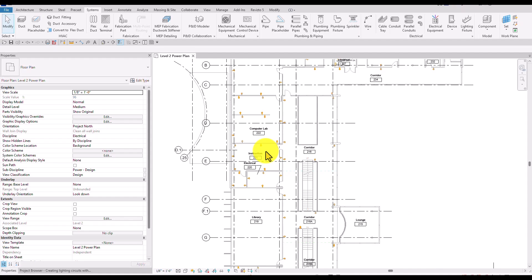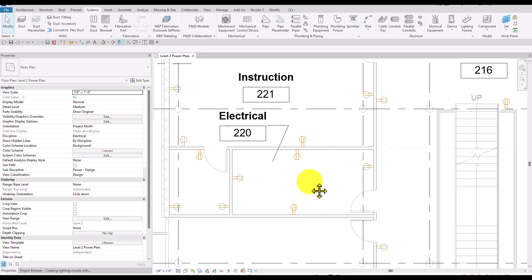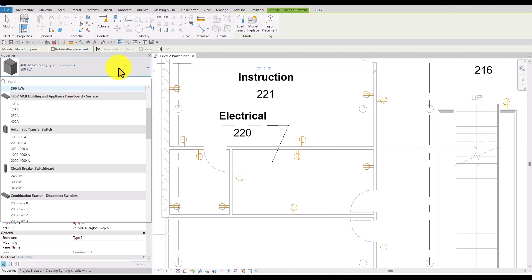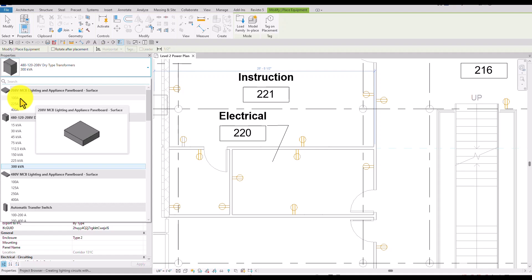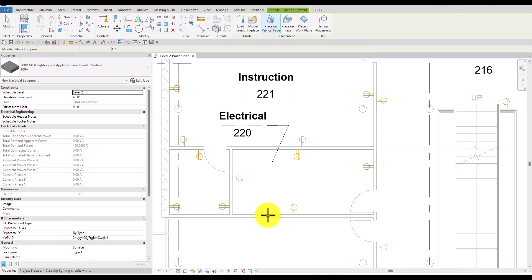Currently I am on Level 2 plan, so I'm going to zoom into this area where I'll place the equipment. From the Systems tab, I'm going to select Electrical Equipment. From the type selector, I'm going to select the 208-volt MCB — Main Circuit Breaker, Lighting and Appliance Panel Board, Surface. This is a surface-hosted family. I'll select 100 amps and make sure the placement is set to Vertical Face. Then I'll click to place it on this wall.